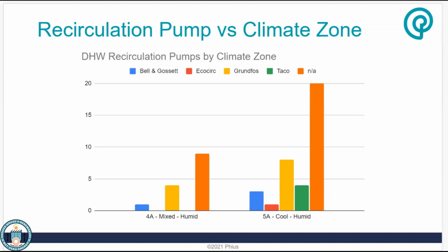Or you can treat on demand as just a pressure drop in the system that will trigger the recirculation pump to start running. That's the more common one we see in multifamily projects.